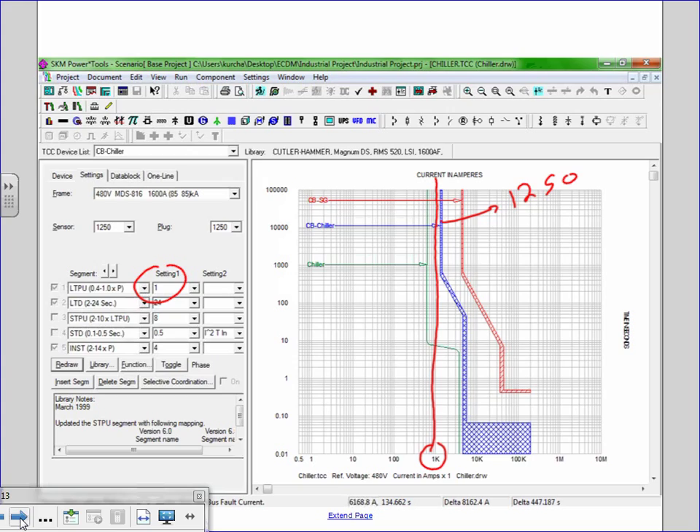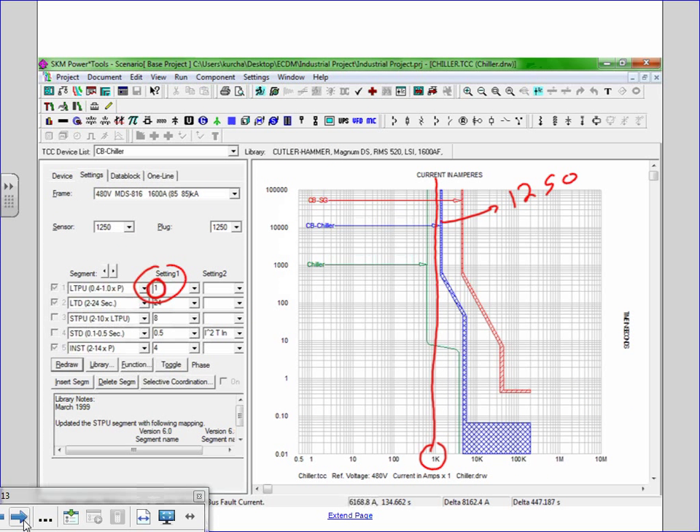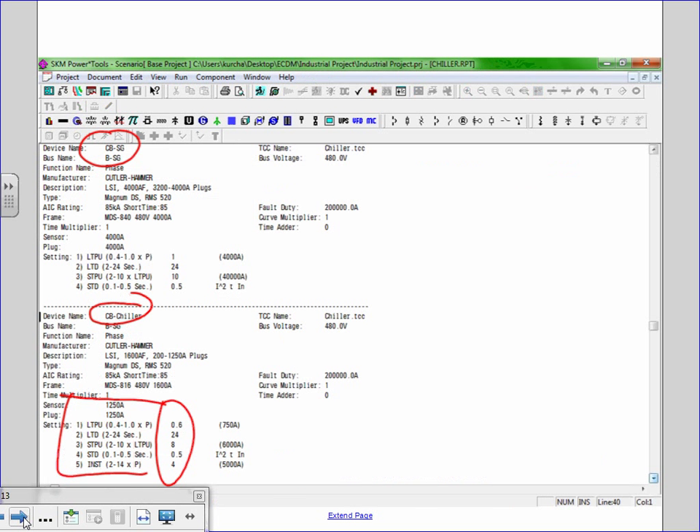Here's your 1,250 amp breaker. If you change the setting to 1, this circuit breaker shifts from 750 amps — which it was at 0.6 — up to 1,250 amps. You're going to be doing that for the commercial project. When you print the coordination report, you'll see: 1,250 amp frame, plug at 1,250, setting at 0.6 giving 750 amps. All those settings get given to Mr. Electrician, who grabs a screwdriver and adjusts the dials.